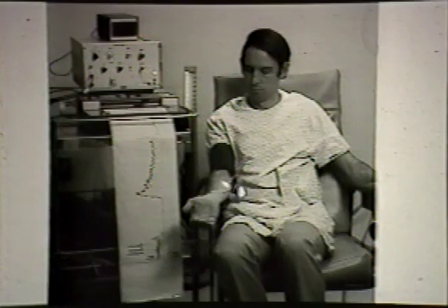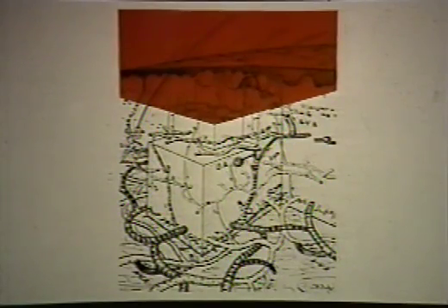You can see a speckle effect, that is interference on your eye that looks like speckles if there's very little flow, but as the flow increases, that speckle starts to dance. And the instrument is basically measuring properties of that fluctuations in the light and measuring our various parameters. Now, when you put light in at a point and then look at it coming out at a nearby point within, say, a half millimeter or a millimeter, the light really tends to go over fairly shallow paths and doesn't penetrate very deeply.